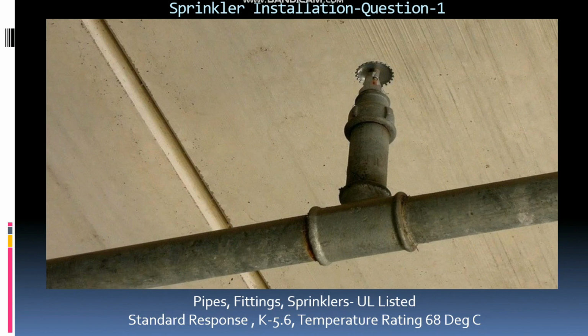In this image, the problem is the frame orientation. This is the frame, so you know that this is the frame. The frame orientation is not parallel with the pipe. It is in the opposite or reverse direction. So this is not acceptable, first of all. The correct installation is that this sprinkler should be rotated 90 degrees anti-clockwise. Then the frame will become parallel to the branch line.